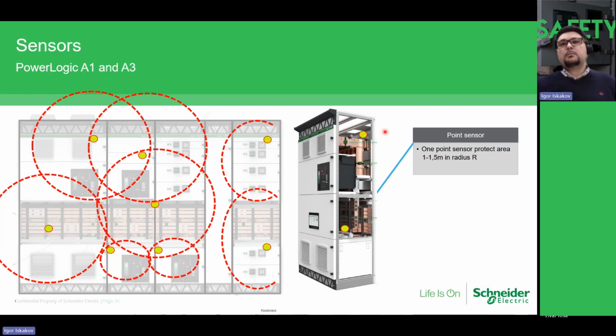And here you can situate the sensor on the top, for example. In some cases you can situate the sensor on the top or on the bottom of your switchgear. So this is also a quite easy installation for low voltage switchgear. During your maintenance break, you can install arc flash protection sensors and secure your equipment and your personnel.